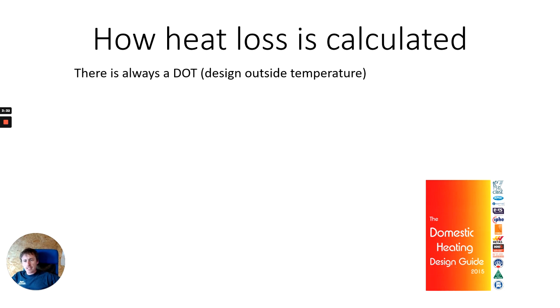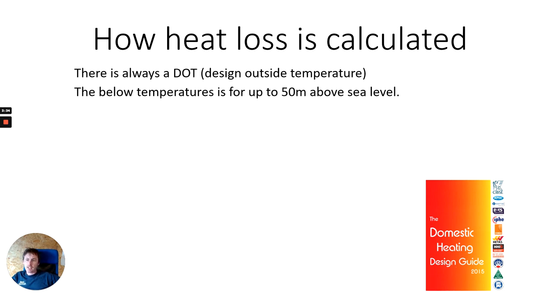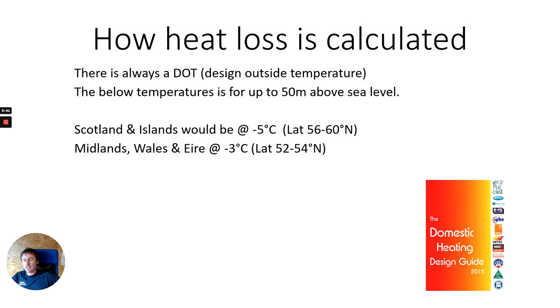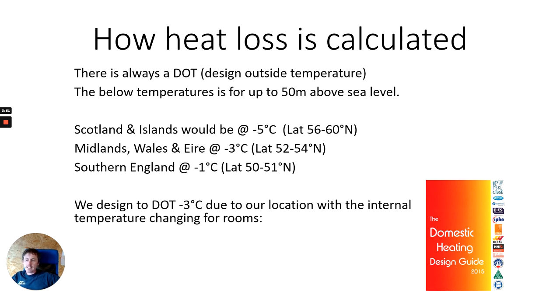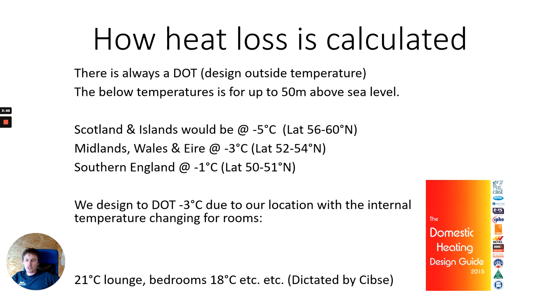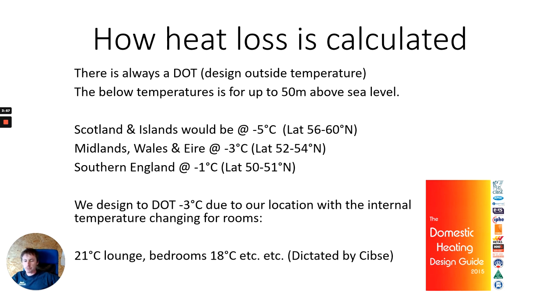There is always a DOT — a design outside temperature. For locations up to 50 metres above sea level: Scotland and the islands would be minus 5°C; Midlands, Wales, and Eire would be minus 3°C; and southern England would be minus 1°C. We design to a DOT of minus 3°C due to our location, with internal temperatures varying by room — 21°C for lounges, 18°C for bedrooms, and different values for bathrooms — all dictated by CIBSE rather than the customer.